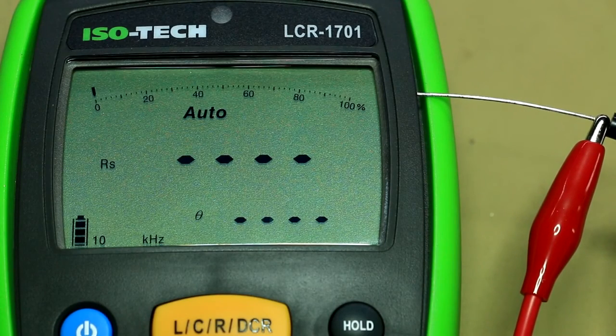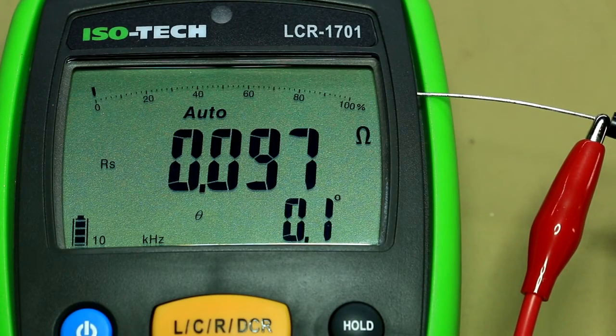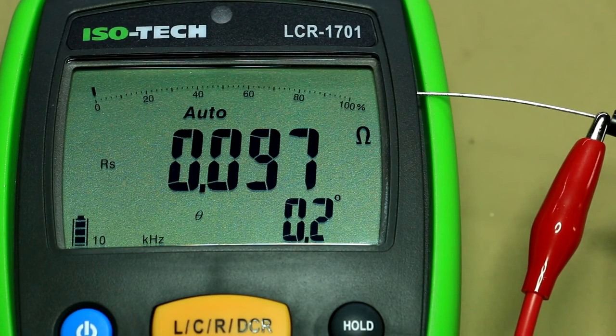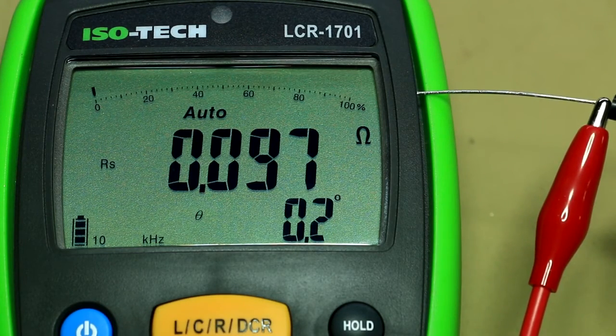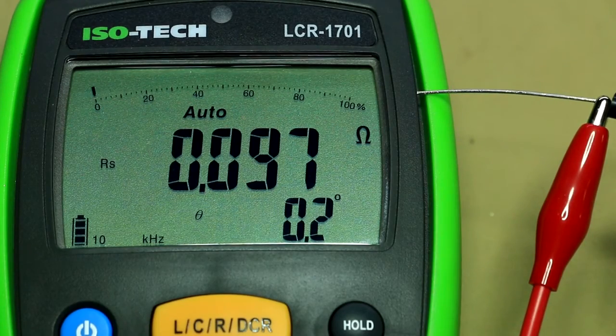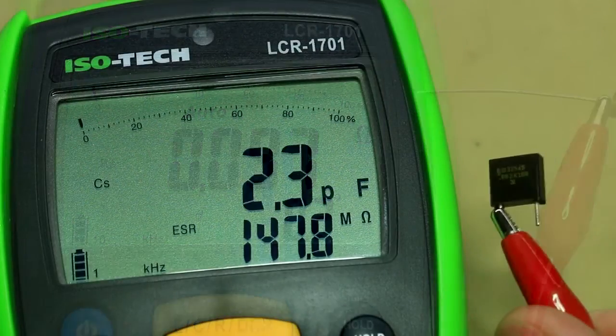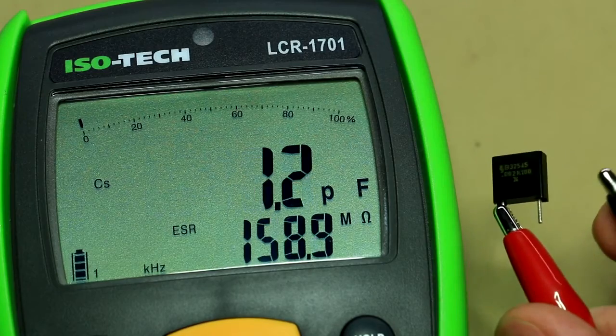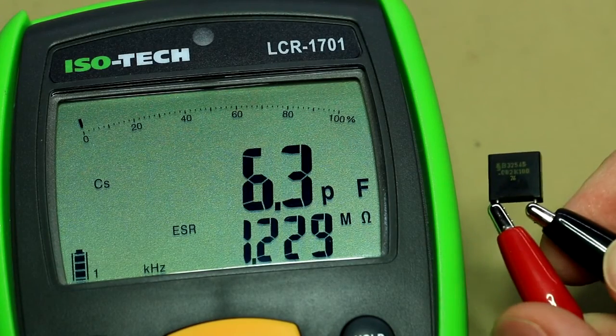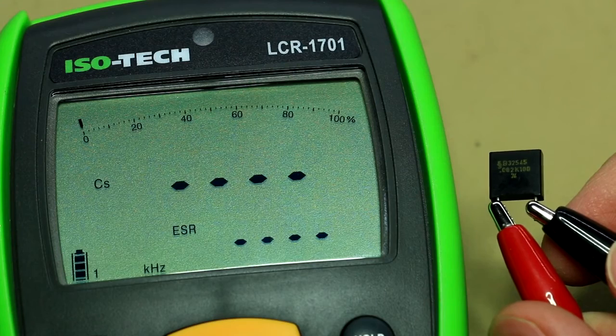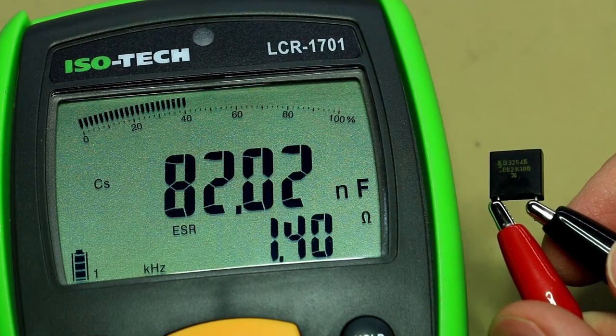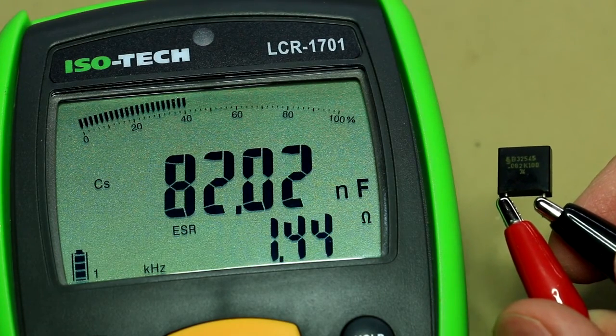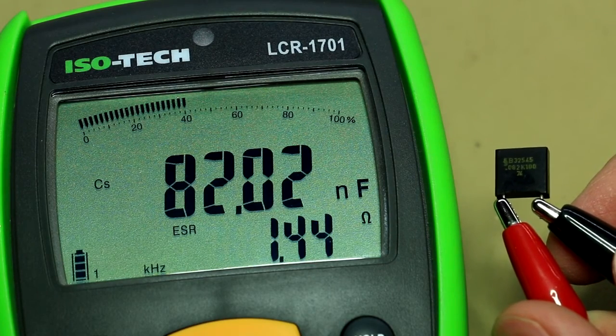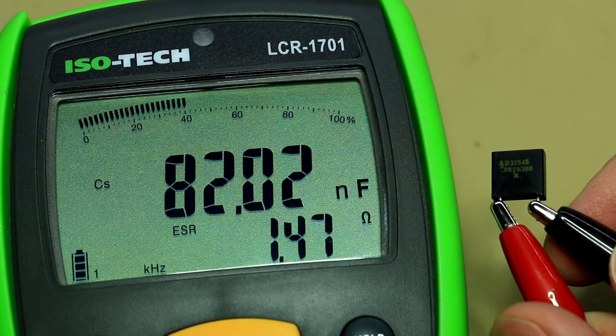Make sure you've got good contact. There we go, 0.097 or 97 milliohms. So it picked up that 3 milliohm difference in the lead wires. Okay, let's measure this 82 nanofarad capacitor. It's a high accuracy capacitor. That's quite spot on, 82 nanofarads at 1.4 ohms ESR.